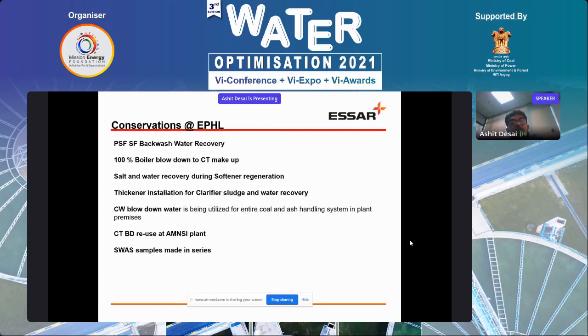To achieve the specific water consumption of 2.2 meter cube per megawatt, we have implemented various water conservation schemes like pressure sand filter and softener backwash water recovery. It is 100% recovery. 100% boiler blowdown water to cooling tower makeup. It is already said. This is a unique one. Salt and water recovery during softener regeneration. It was found that some amount of salt and water can be recovered during the regeneration based on some testing carried out at site.